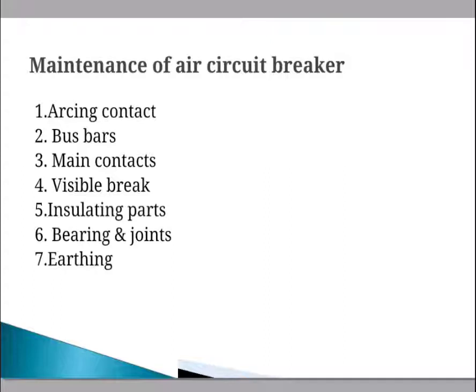For the bus bar, tighten any loose joints found — carried out half-yearly. For main contacts, file the contacts and clean the surface with petrol or recommended chemical, then lubricate with a suitable lubricant such as Vaseline if necessary. This is carried out half-yearly.